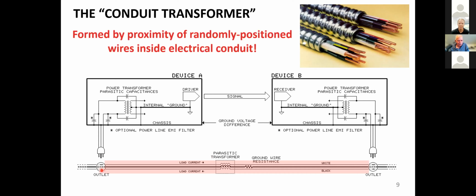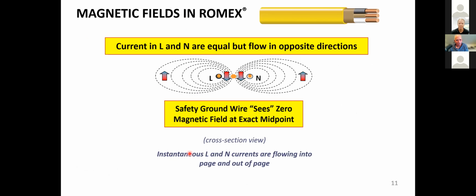It's simple to analyze a single instance of this happening. But if there's current flowing down one of these conductors and coming back on the other one, there are two magnetic fields. And they will, by transformer action, induce a voltage on this third conductor running in there, unless it happens to be positioned precisely in the middle. And even with ROMEX, we can't guarantee that. Even putting a twist and turn in ROMEX disturbs the position, because a few thousandths of an inch of movement will upset everything.